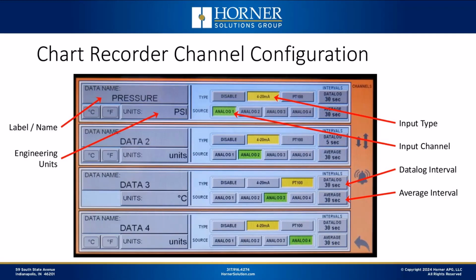On the upper right-hand corner there, you can see that for each of the 4 channels, you can configure the input type. Is it a 4 to 20 milliamp raw input signal coming into that first channel there? Or are you going to connect a RTD PT100 to that channel instead? Because that's an option as well. PT100 sensor, temperature sensor, at least of limited temperature range, -50 to +200. If you need a wider temperature range than that, then you can use an RTD transmitter connected to 4 to 20 milliamps and display it that way.